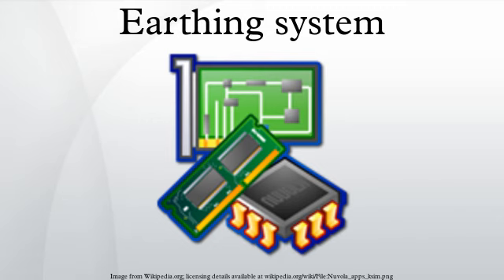IT network: in an IT network, the electrical distribution system has no connection to earth at all, or it has only a high-impedance connection. In such systems, an insulation monitoring device is used to monitor the impedance.